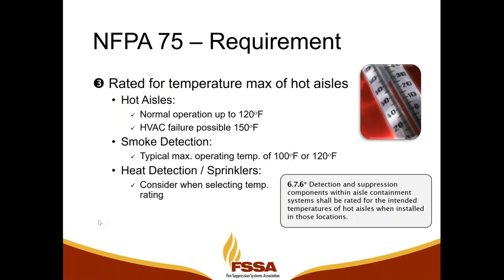Now understand, this really affects smoke detectors and sprinklers. The maximum operating temperature of most commercially available photoelectric spot smoke detectors is 120 degrees Fahrenheit. We can exceed that. That means that the detector may not operate to see a fire. And understand, as the surface temperatures increase, the likelihood for ignition also goes up. So that's maybe where we see our fire in the data center.